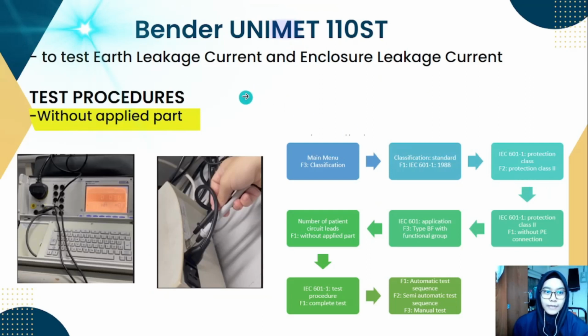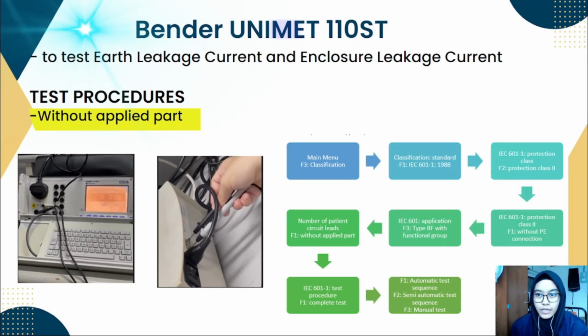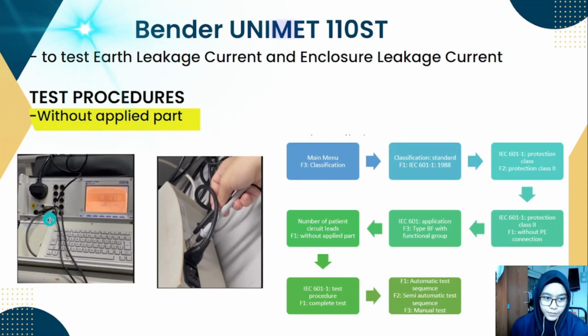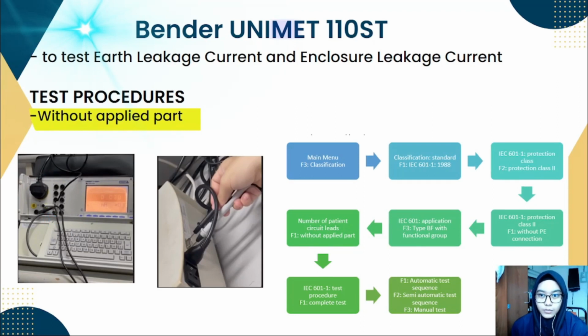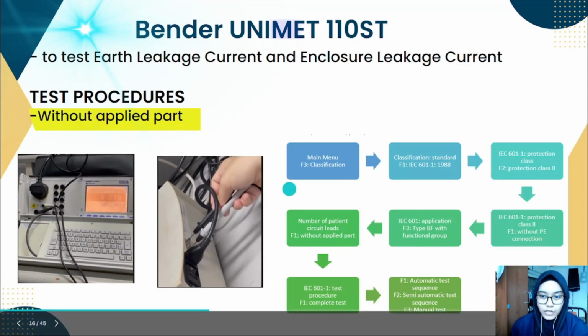First, we use the Bender to test earth leakage current and enclosure leakage current for the without applied part. First, the Bender safety analyzer will connect to the tonometer, and then the 3-pin plug of the tonometer will connect to the Bender, and there will be probes connected to the conductive part and the earth of the tonometer. Then we can start the test by following this flowchart.